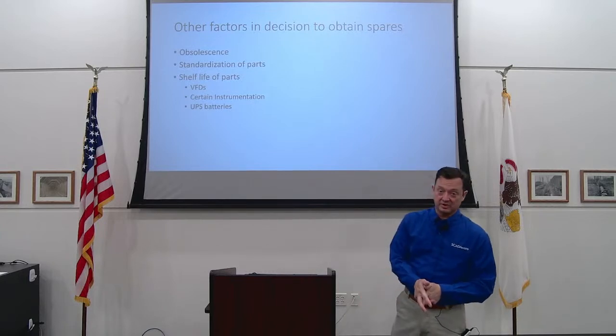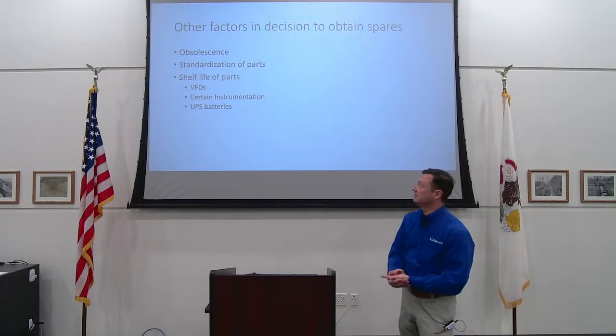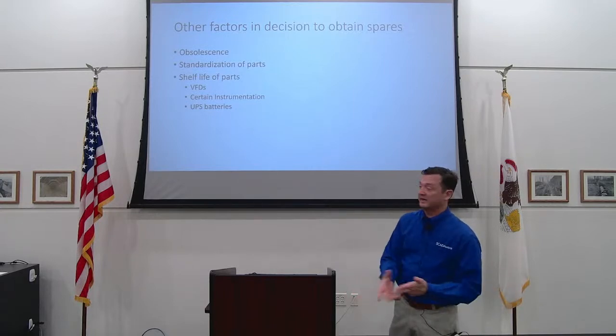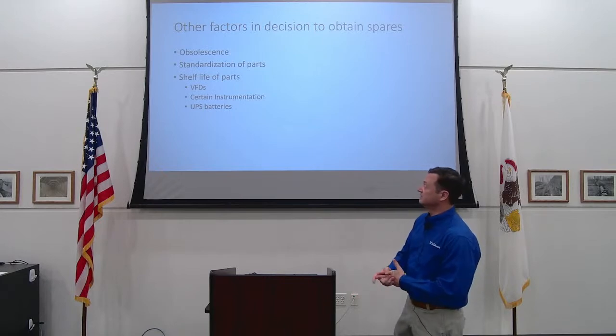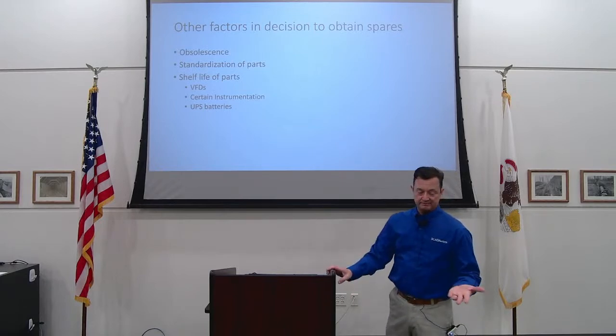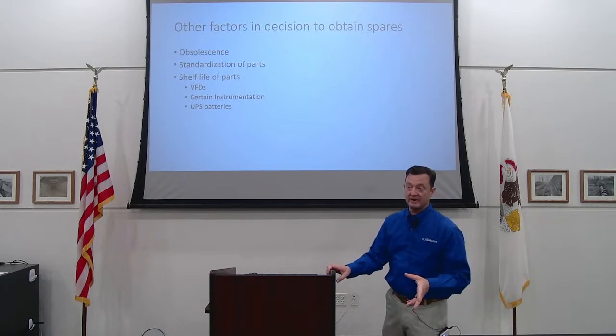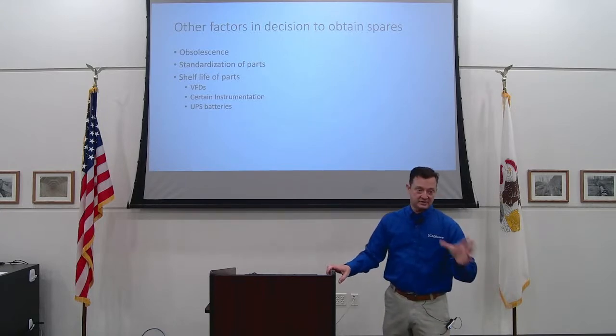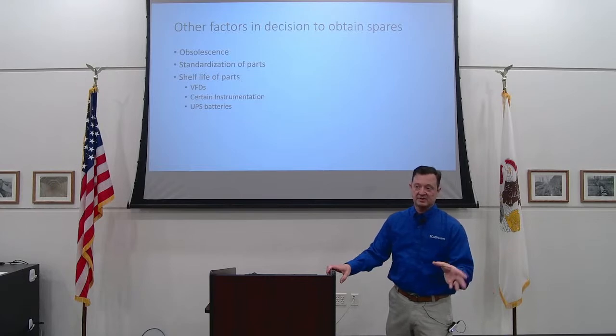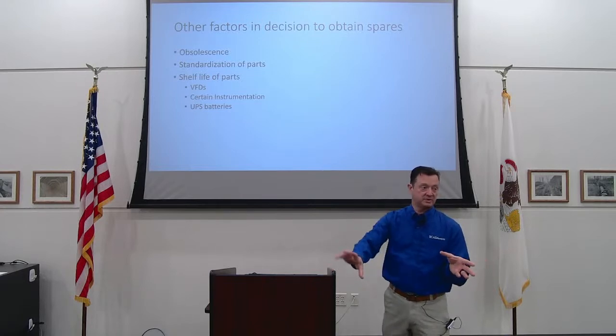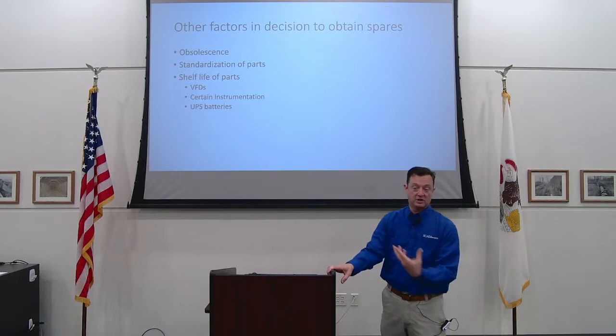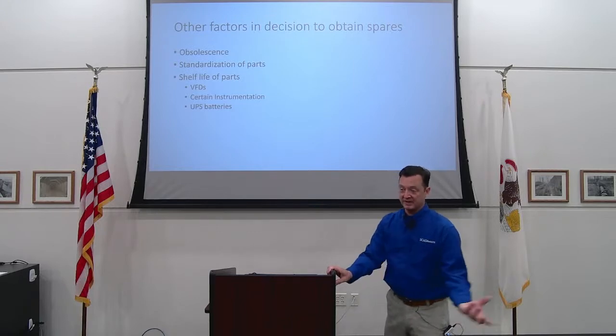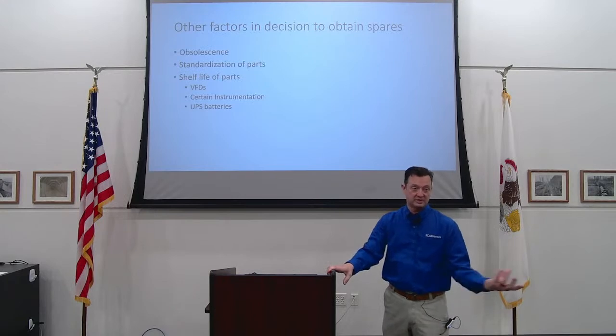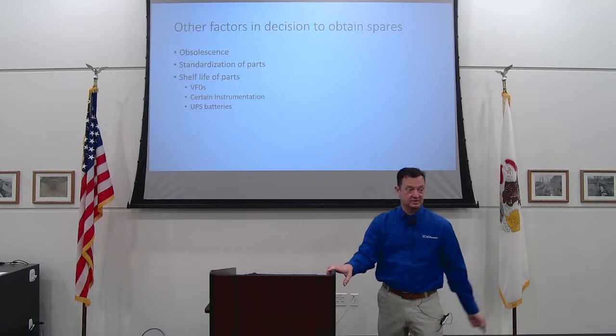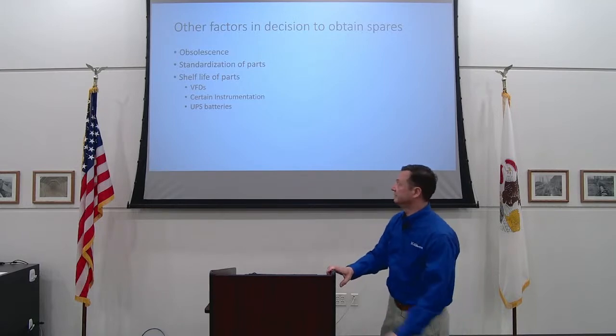Look at standardization of parts so you try to use the same things in many places as possible. Also look at shelf life of parts. I don't know if this is well known, but I've been told by some of our vendors that a VFD sitting on the shelf has less of a lifespan than the VFD that's in service, because the capacitors on a VFD need to be charged. So if you put a VFD on the shelf thinking you've got a good spare part, there's actually a really good chance that it's going to pop as soon as you install it.